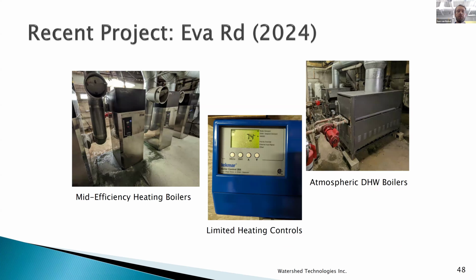So just to highlight one recent project that we did for a building on Eva Road, this was done last year. Before the project, the building had mid-efficiency heating boilers, which are quite typical for the space heating system, atmospheric domestic hot water boilers, and a tekmar control, which is a sort of limited control that does some outdoor reset, but can't be accessed remotely and really can't be adjusted that easily.